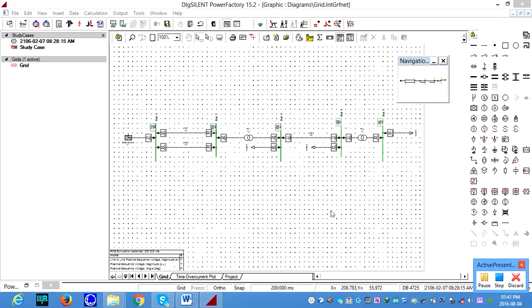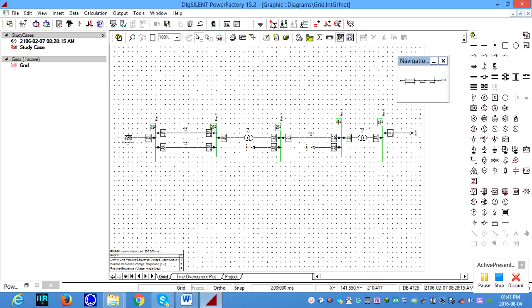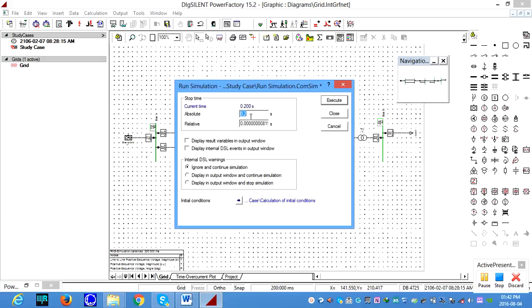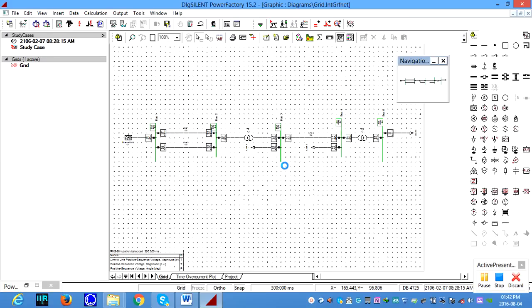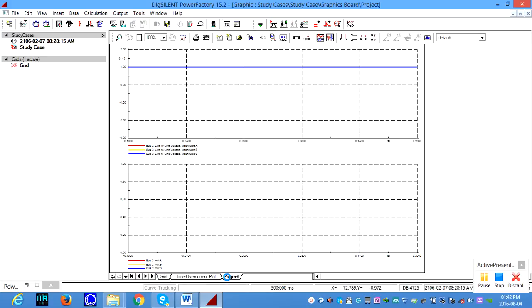Okay, now we need to validate or verify the voltage and the current waveforms for the fault condition or for the normal operating conditions. This is the tool where you can select RMS and EMT simulation, and you can set the calculation time here, let's say 0.3 seconds, and you just execute the simulation. You can go to the plot.